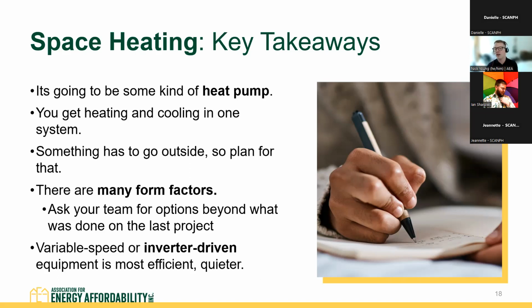Kind of, not really. The packaged rooftop unit is the heat pump version of a rooftop package unit. A rooftop package unit is by far the most common commercial heating and cooling system in the country - you see it on top of every Best Buy, every Target, every big box store ever, and there are some in multifamily buildings too. Usually those are an air conditioner with a gas heater, and you can do the same with a heat pump. They're sometimes a slightly larger form factor than the gas version, because the heat pump needs to absorb heat from the air to do the heating, instead of just pumping gas into a furnace. It has to pull that heat from the ambient air on the roof, so the rooftop heat pump package unit can be slightly larger than a rooftop gas-fired package unit, but it's a bit of a different system than the ducted heat pump. Usually though, those package units are ducted.